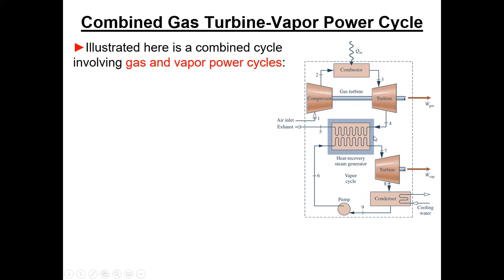So we're going to put in this, it's called a HRSG, a heat recovery steam generator. HRSG is the terminology. And you'll hear people in the industry talk about HRSG. And that's what we're talking about. So basically, this heat recovery steam generator takes the place of the boiler. So in this simple cycle, we're only burning gas up here in the gas turbine.